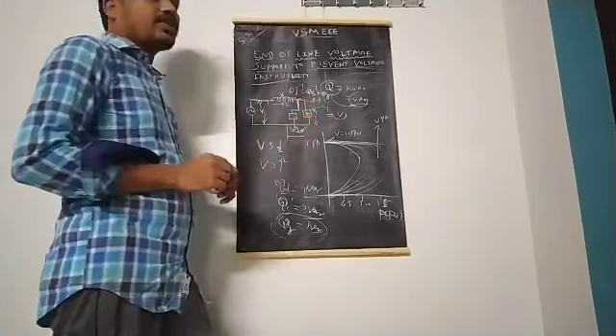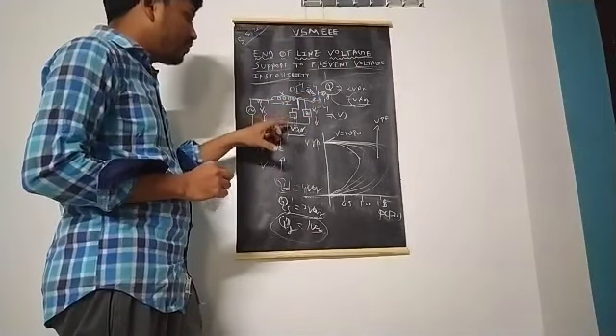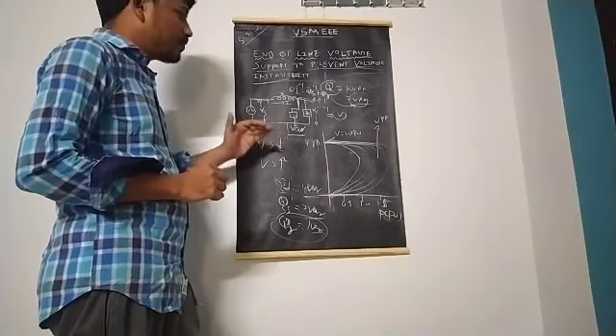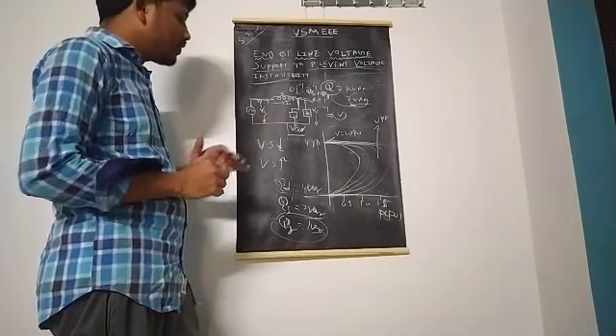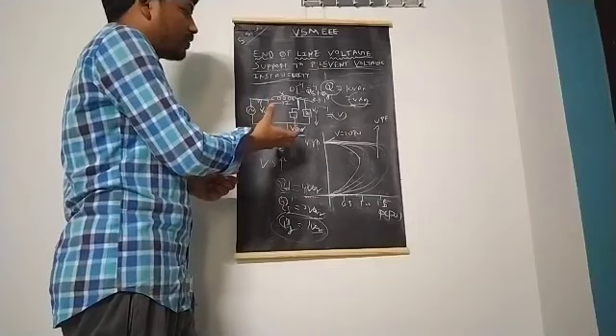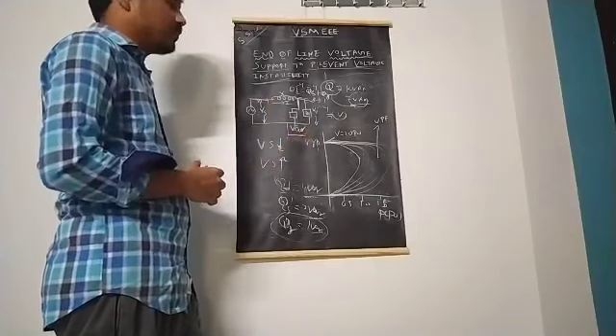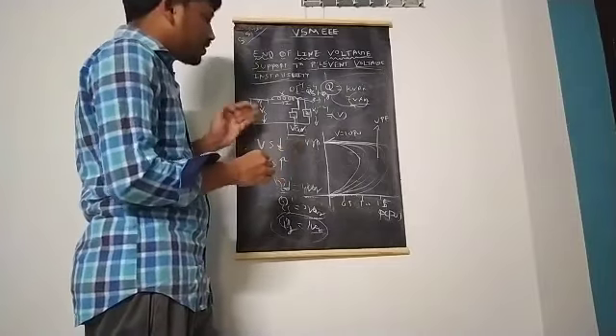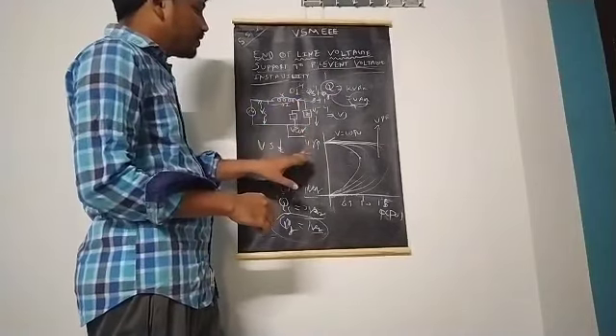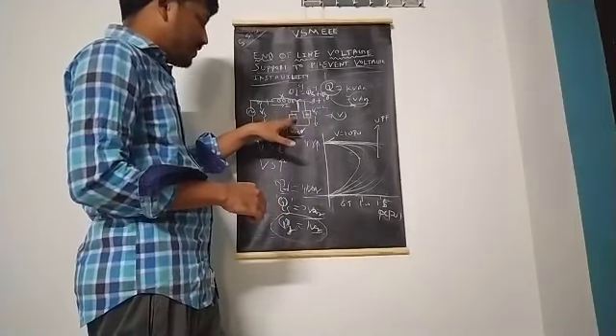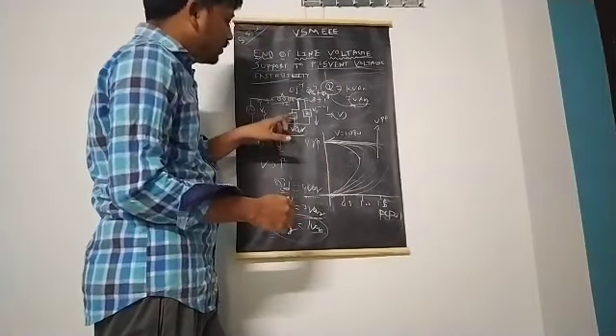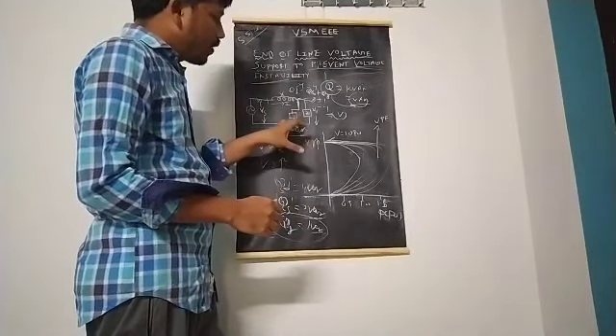This is the issue with the variable impedance type of compensation devices used at the receiving end side — at the end of the radial transmission line. At the radial transmission line, the ending point uses the variable impedance type, which may be inductance or capacitance. In this way, the shunt compensating device provides reactive power and thereby improves the voltage profile of the system. In the last class, we discussed the system and the P versus V curve without any compensating devices. But in this class, we discuss what happens to the P versus V curve while connecting the shunt compensating devices.